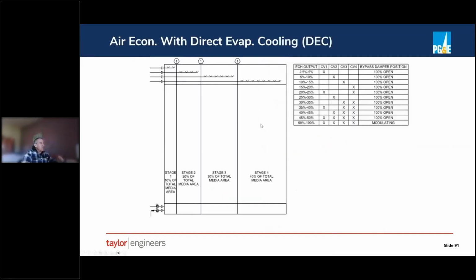So back to how do you modulate direct evap? This is a design from another engineer's drawings of a direct evap system where they had split the media into 4 stages of different sizes, right? This one was 10% of the total area, 20, 30, 40. And then it came up with this sequence here. As your PID loop output increases, the first step was to start with just this 10% stage. The next step was to turn off the 10% and turn on the 20% stage, then turn on the 30, 40, etc. And this was before even starting to modulate the bypass damper. The bypass damper was the last part of their mapping.